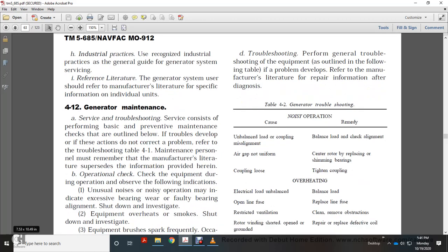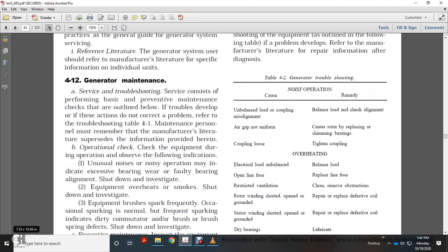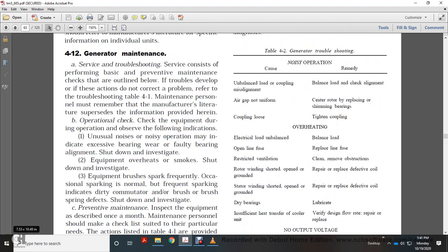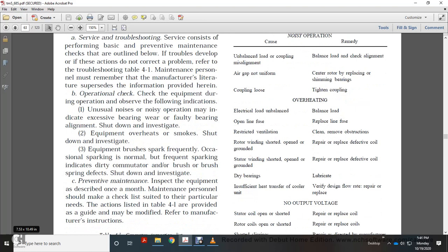Observe the following indications. Unusual noise during operation indicates excessive bearing wear, a faulty bearing, or alignment problems: shut down and investigate. If the equipment overheats and smokes, shut down and investigate. Check the brushes for smoke. Occasional sparking is normal, but frequent sparking indicates dirt, a commutator problem, or a brush and brush spring defect. Shut down and investigate. Preventive maintenance: inspect the equipment described once a month.